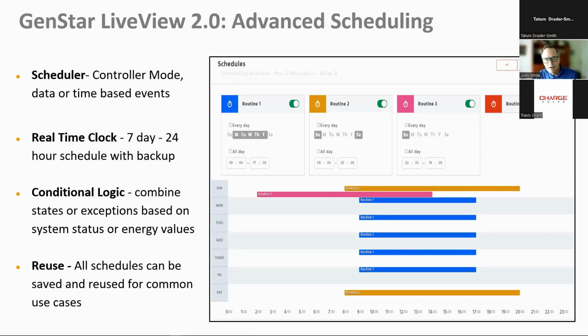This is an example of some of the advanced scheduling we have. Based on the real-time clock, we now have 24/7 capability to schedule the controller based on time events. You can use the conditional logic we talked about, reuse these schedules, and save them for different cases. You can overlay and look at a weekly calendar from LiveView showing the different routines and settings for turning on loads, multiple load controls, state of charge information, low voltage reconnect voltages, and everything like that.